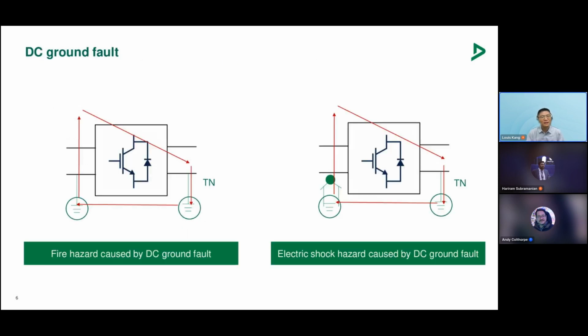DC ground fault can cause both fire and electric hazards. The rationale is, if a non-isolated PV inverter is used in a TN system, insulation failure on a PV cable could lead to high current on the grounding path, which will further result in a high temperature in the grounding cable or high current in the human body.